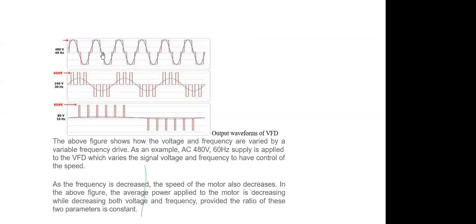Let us take from here to here. Let us consider this is 50 cycles. Now, if this 50 cycles is not reduced, then we cannot reduce the speed of the motor. And this 50 cycle in AC format is not possible to apply for reduction of speed. So what we do here, we convert this sinusoidal curve to a DC curve, or direct current.